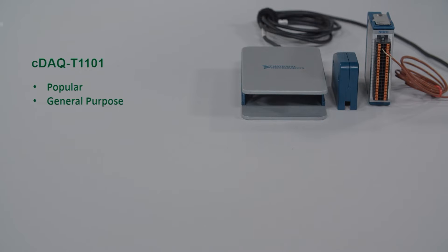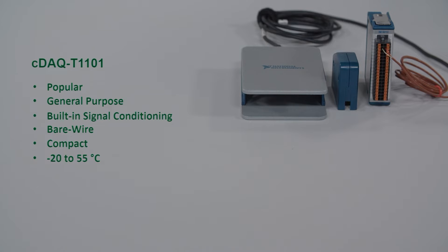So let's look at the bundle. We have the cDAQ-T1101, which includes our most popular general purpose thermocouple measurement hardware. It has built-in signal conditioning for your thermocouple's needs, such as built-in isolation and cold junction compensation. You can also directly connect a thermocouple with bare wires into the spring terminal — no soldering or screws required. This entire bundle is very compact, so it won't take up much space, and you can port it to different labs when you need to.